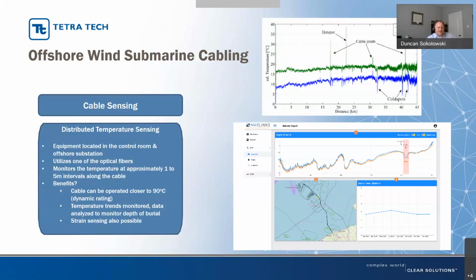Why would you want to do that? Cables can be operated up to a maximum temperature of 90 degrees Celsius for an XLPE insulated cable. If you go over that, you risk damage to the insulation. So a distributed temperature sensing system can show any hot spots along the cable—maybe the burial's got deeper, or maybe the cable's over something metallic causing a hot spot you don't know about, things like that.